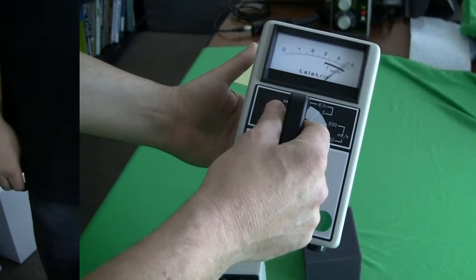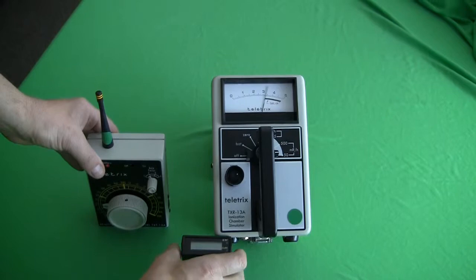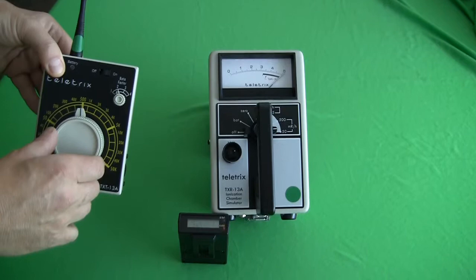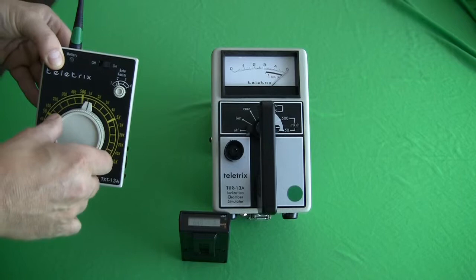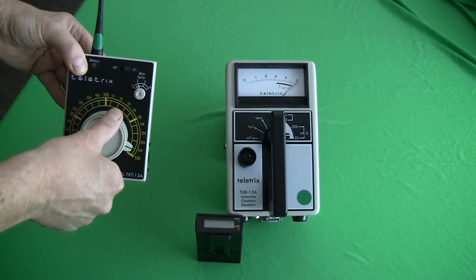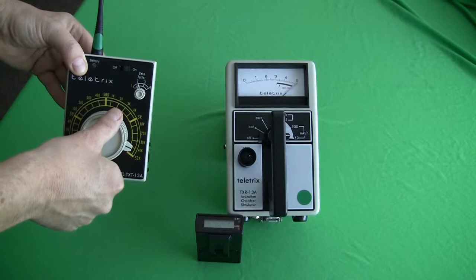The SD900 simulated alarming dosimeter works in conjunction with this system. Note the rate alarm as we hit the rate alarm set point, and as we back away from it, it extinguishes. We hit it again, and then the exposure rate is set so that we hit the dose alarm in a short period of time. Note the on-off status and the retention status of the alarm.